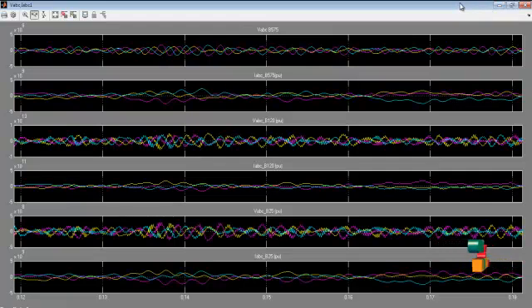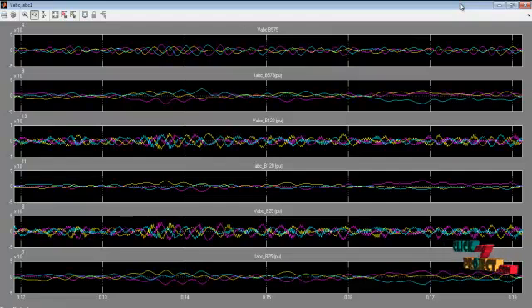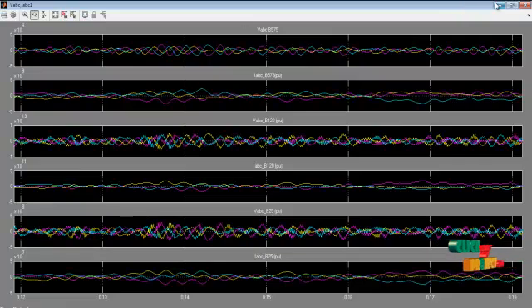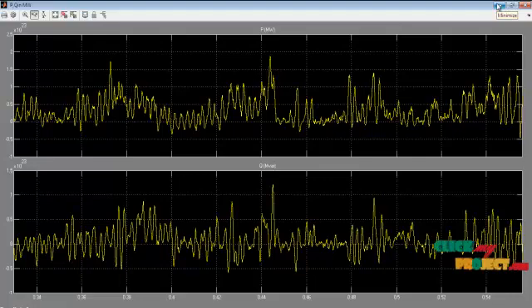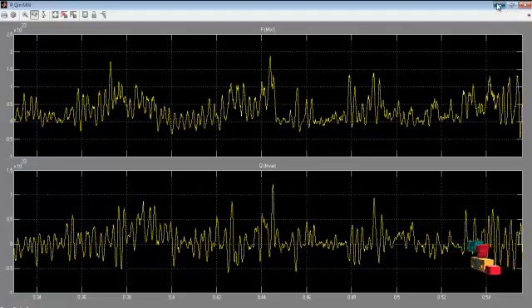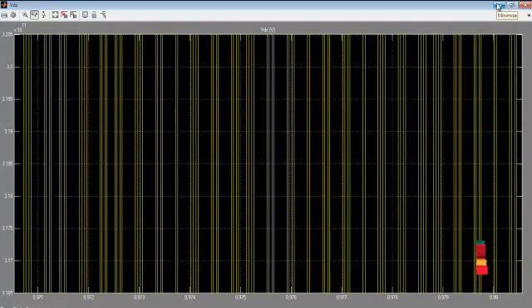The next one is the IABC for the 575 V bus. The next one is the 120 kV bus voltage and current waveform. The next one is the 25 kV bus voltage and current waveform. The real and reactive power are calculated from the grid side. The next one is the VDC voltage — this is the DC link connected between the Grid-Side Converter and Rotor Side Converter.